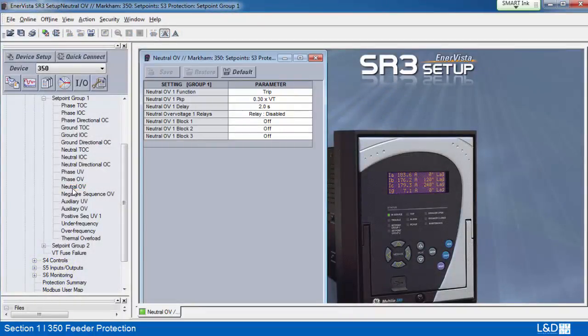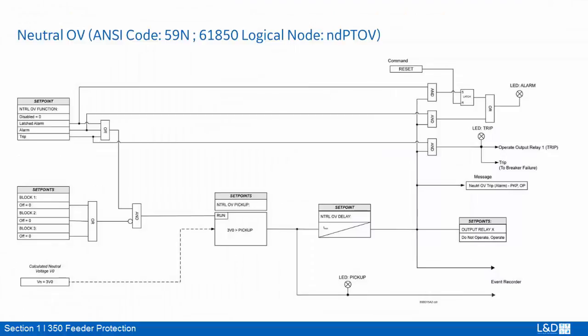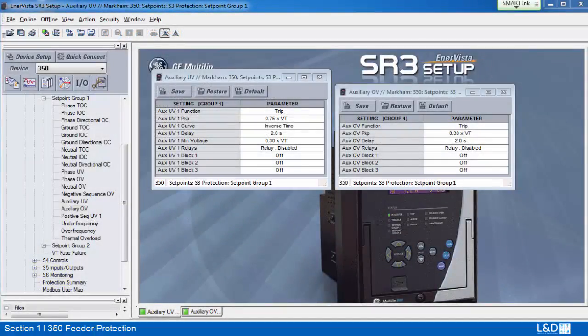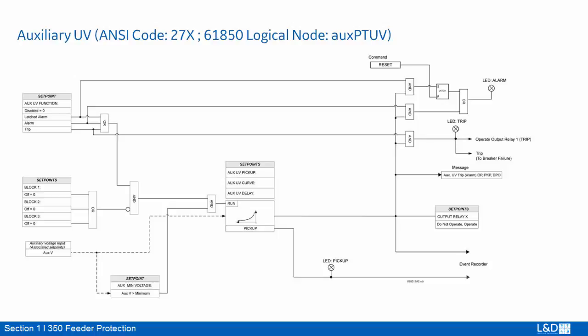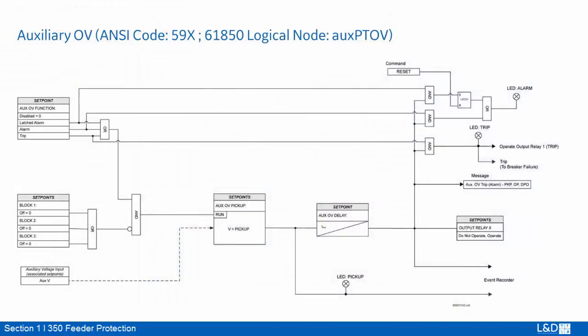The neutral overvoltage of the 350 relay requires the three-phase bus VTs to be Y connected. It has pickup and delay settings similar to phase overvoltage. When setting the pickup for this element, it is important to consider the error in VT ratios as well as the normal voltage unbalance on the system. The logic diagram shows the input neutral voltage is 3V0. Auxiliary undervoltage and overvoltage use the input from auxiliary VT relay terminals VX, where a single voltage from the line is connected, and all settings are the same as phase undervoltage and overvoltage.